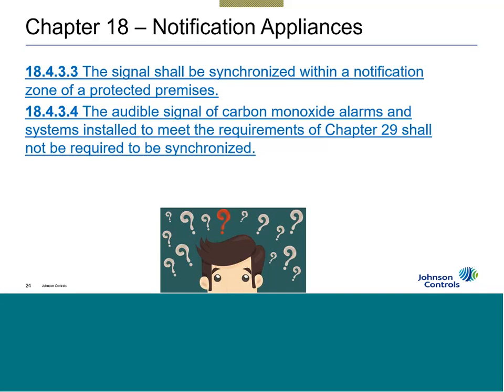The problem might occur, though, where you take a notification appliance extender panel, tie it into an older hardwired fire alarm, and you're trying to synchronize devices together. You might need synchronization modules or some other way of making sure that your NACs are synchronized together. So just be aware that going forward here in 2019, they all need to be synchronized for audible in a notification zone. Not the whole building, just the notification zone. Notification zones are made up from signaling zones, signaling circuits. You can have 3 signal circuits that create a notification zone. And for carbon monoxide alarms, the requirements in Chapter 29 do not require synchronization. Chapter 29 is a whole separate animal, and they kind of do what they want over there.